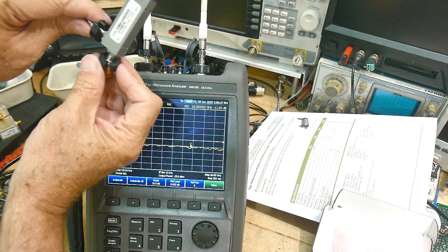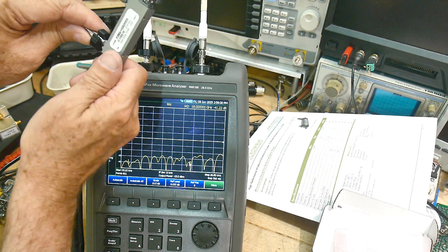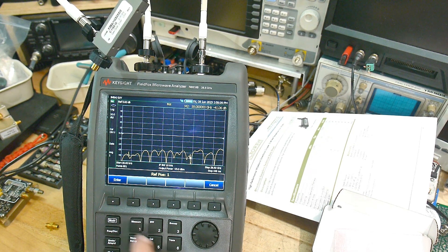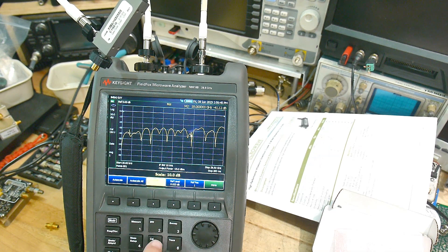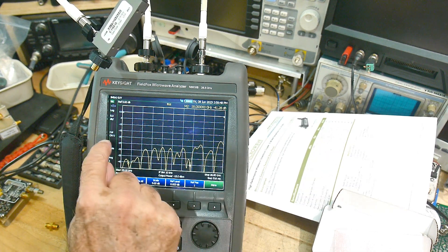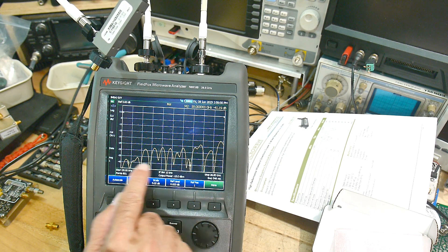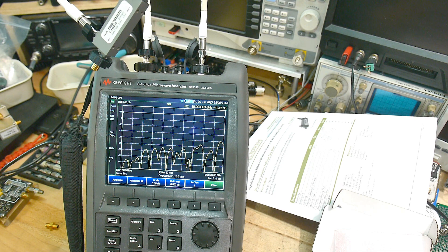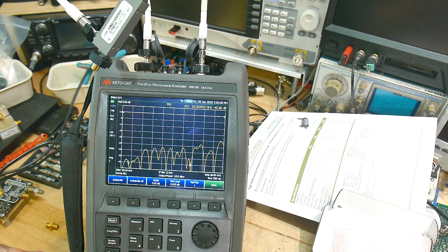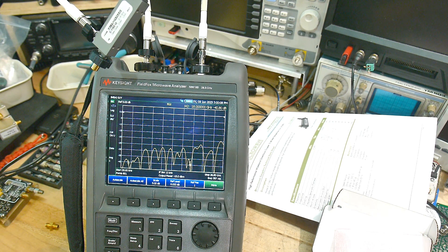And we will come here with our—oh yeah, it's much better. Let's do a scale. Let's move this up here and let's do a scale of 5 dB. Yeah, my worst case is up here at 26 gigahertz. So here's the marker for 18, here's a marker for 2. So yeah, it's better than 25 dB directivity, so it's much, much better than their absolute guaranteed. So this one's operating really, really well.